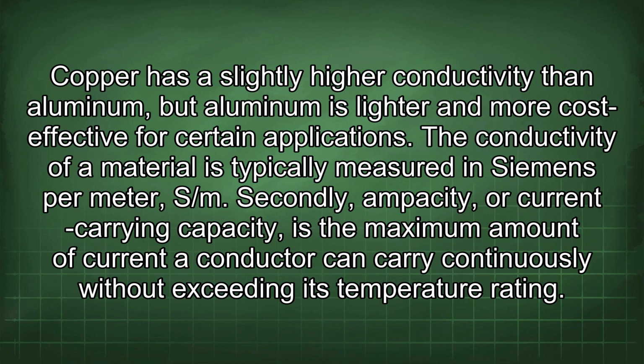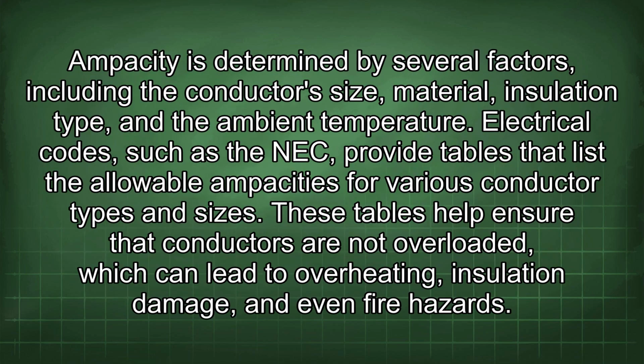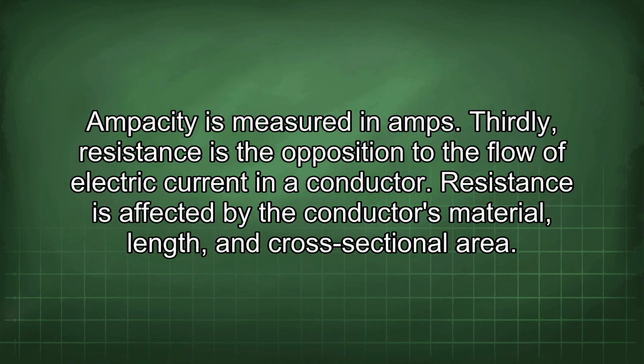Secondly, ampacity, or current carrying capacity, is the maximum amount of current a conductor can carry continuously without exceeding its temperature rating. Ampacity is determined by several factors, including the conductor's size, material, insulation type, and the ambient temperature. Electrical codes, such as the NEC, provide tables that list the allowable ampacities for various conductor types and sizes. These tables help ensure that conductors are not overloaded, which can lead to overheating, insulation damage, and even fire hazards. Ampacity is measured in amps.